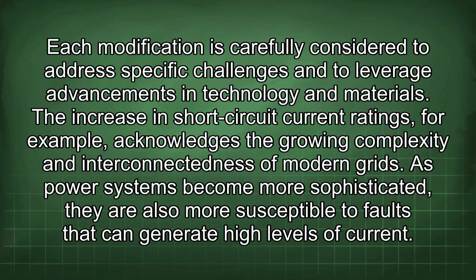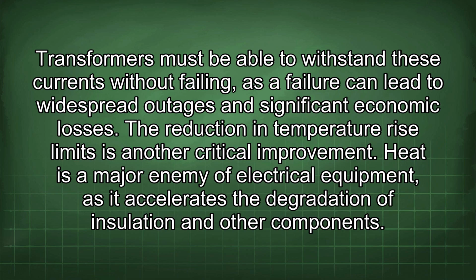The increase in short-circuit current ratings, for example, acknowledges the growing complexity and interconnectedness of modern grids. As power systems become more sophisticated, they are also more susceptible to faults that can generate high levels of current. Transformers must be able to withstand these currents without failing, as a failure can lead to widespread outages and significant economic losses. The reduction in temperature rise limits is another critical improvement.